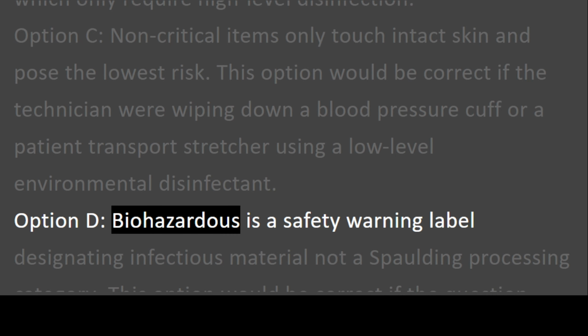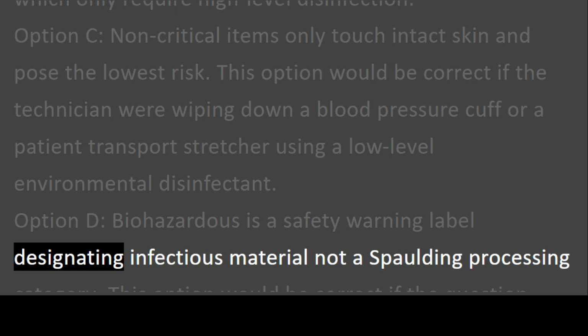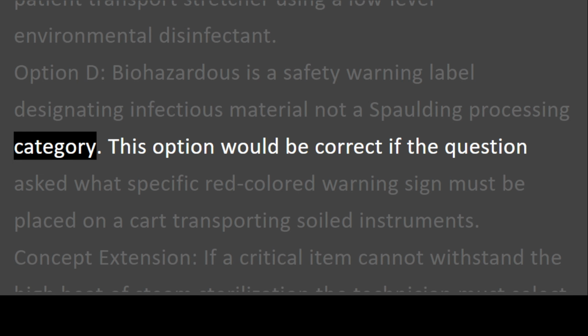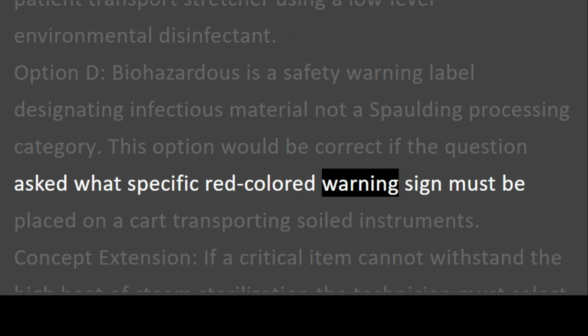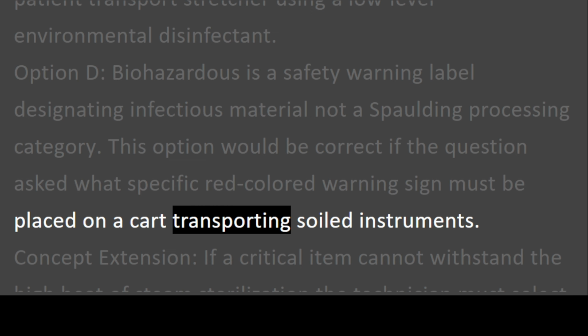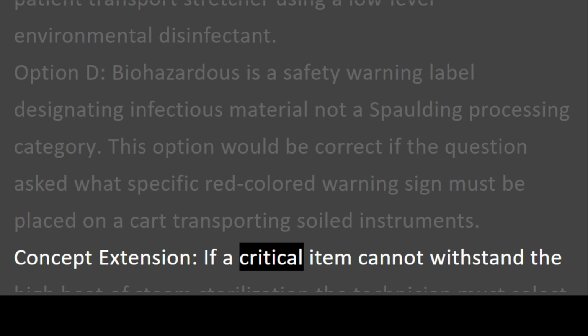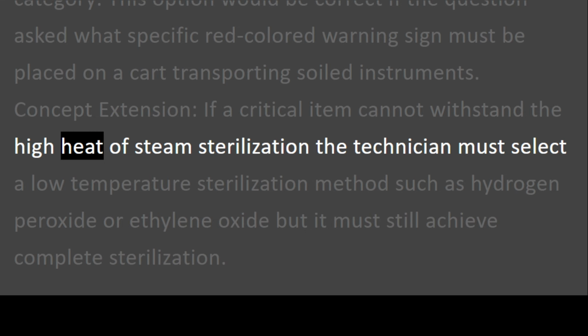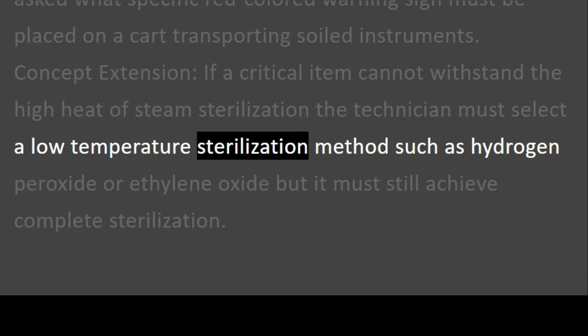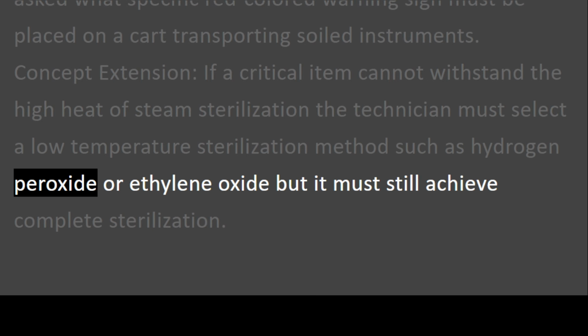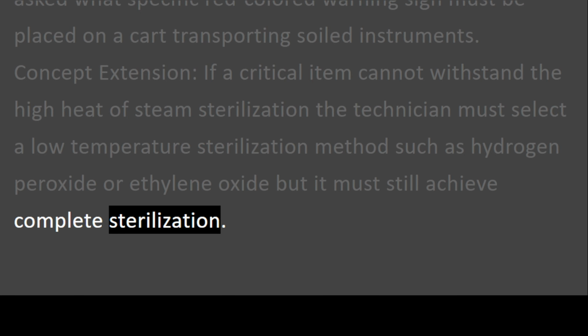Option D. Biohazardous is a safety warning label designating infectious material, not a Spaulding processing category. This option would be correct if the question asked what specific red-colored warning sign must be placed on a cart transporting soiled instruments. Concept extension. If a critical item cannot withstand the high heat of steam sterilization, the technician must select a low-temperature sterilization method such as hydrogen peroxide or ethylene oxide, but it must still achieve complete sterilization.